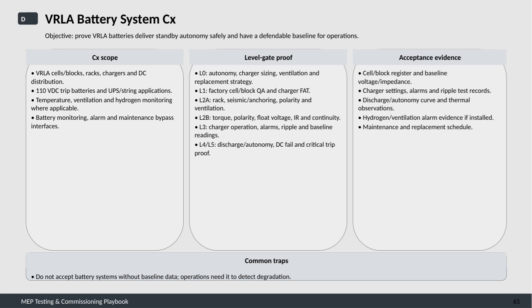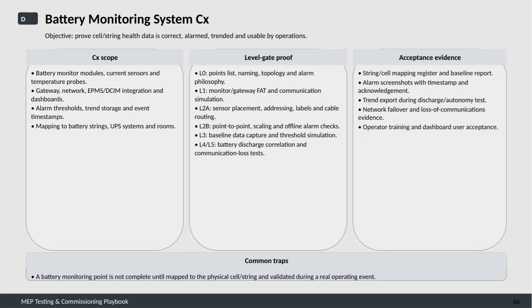A key warning to remember is to never accept battery systems without baseline data. This baseline is essential because it allows operations to detect any battery degradation early, ensuring reliability and preventing unexpected failures down the line. Let's dive into the battery monitoring system commissioning process.